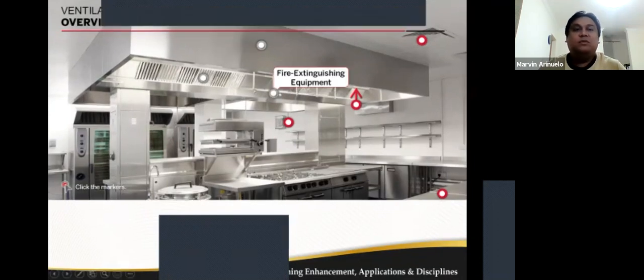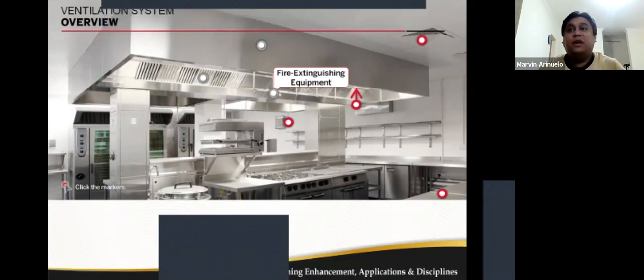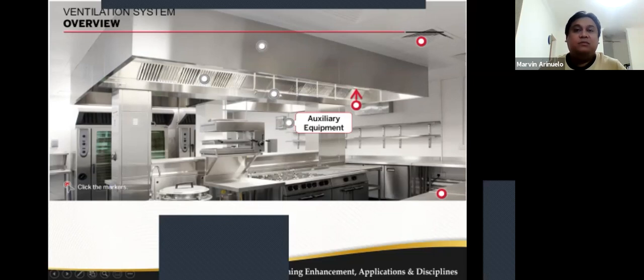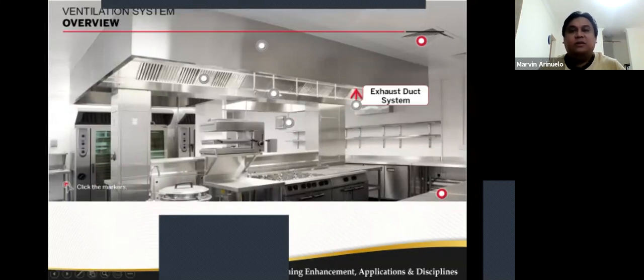Fire extinguishing equipment, or your kitchen suppression system, with nozzles. Basically it's about type K fire, meaning liquid, normally oil-based fire, including animal fat and plant-based fats. Okay, auxiliary or extra equipment, like a maintenance panel. It can be anything: door holder, special sealing requirements, or maybe an automatic equipment shutdown during emergency, and the exhaust duct system as well.